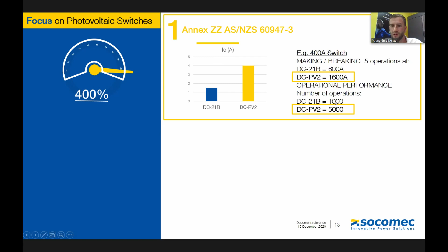However, in Australia, there is a requirement for DC PV2 utilization category driven by the standard, which requires 4 times or 400% of nominal current making and breaking operations. So this means if you want to have the right product for Australia, even though it only gets used at 400 amp, you need to prove that you can switch 1,600 amp in this device. Secondly, in terms of operational performance, similarly, IEC DC21 requirements is 1,000 operations with the Australian requirement 5,000.